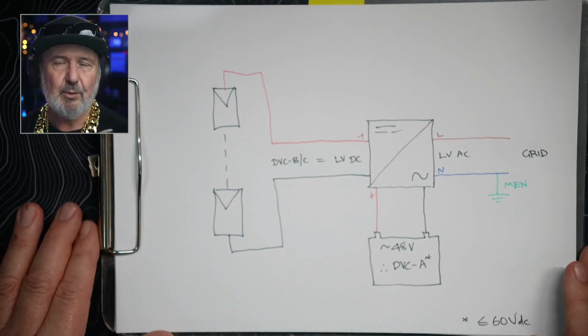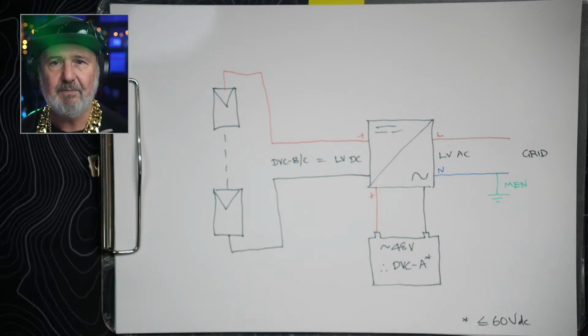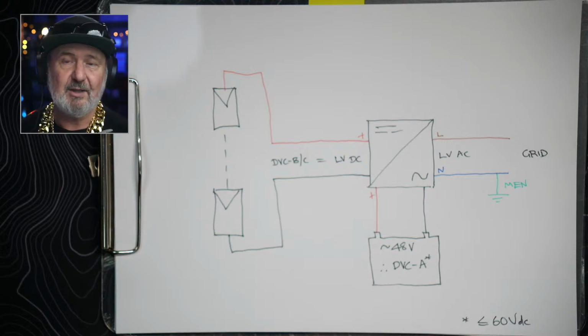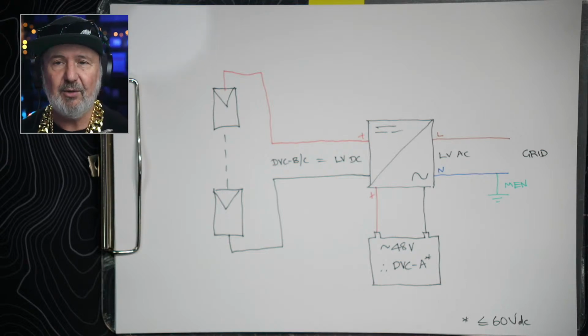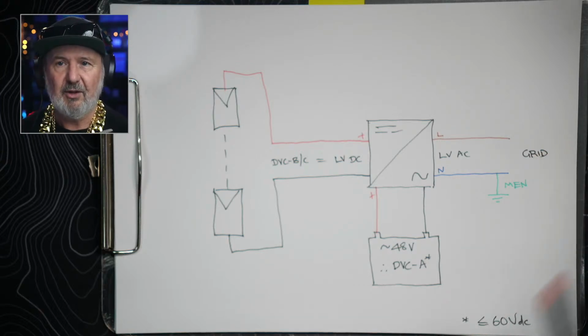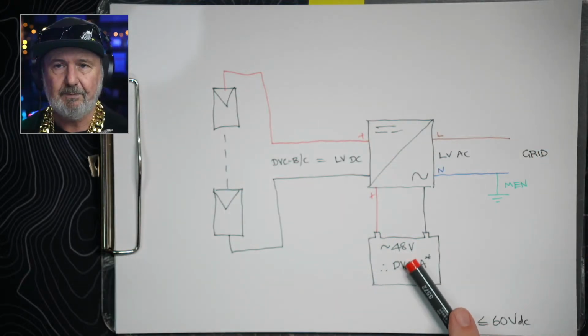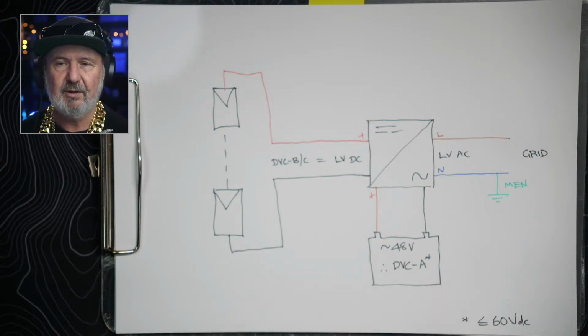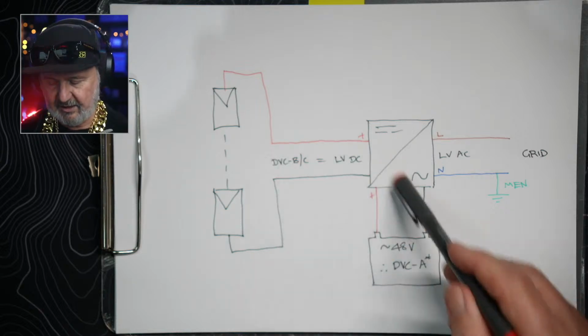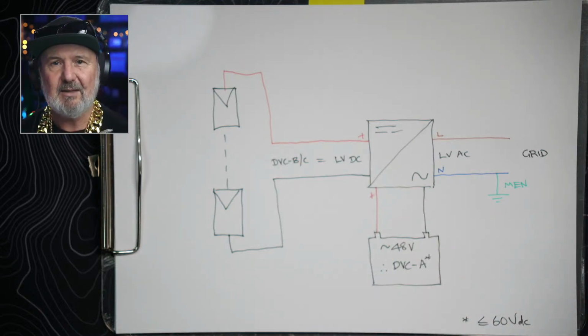These all come from IEC 62109 Part 1, which has definitions for risk based on voltage type, like AC or DC, voltage level, number of volts, and environment, wet, dry, or damp. And so from that matrix, there are different voltage ranges for DVC-A, B, and C, depending on the environment, for instance. And of course, we've got the grid over here. So we've got basically two LV sources here. Now, if there isn't galvanic separation from this battery, then we can have a potential fault that will bring AC or DC onto the terminals of this battery. Now, DVC-A is deemed to be non-hazardous, and so single insulation. In many jurisdictions, it's not even licensed electrical work.